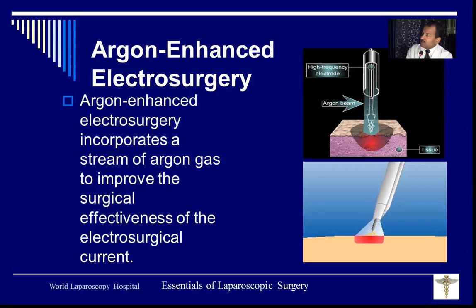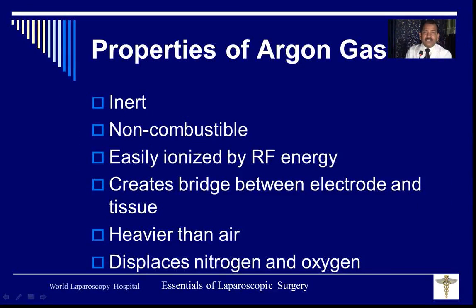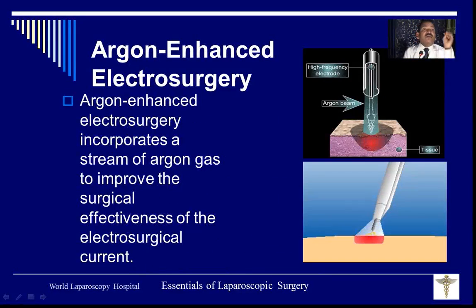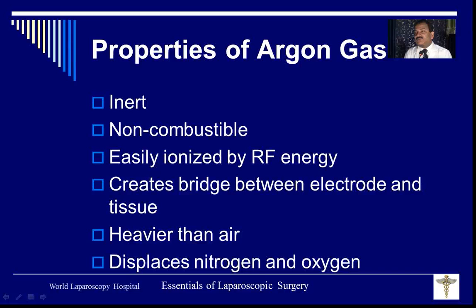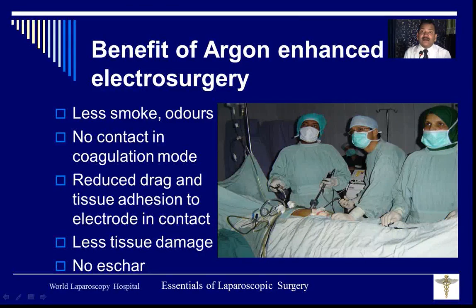In the argon beamer there is a tube outside which will blow the argon gas. Argon gas has a property that it is an inert gas. It is a non-combustible gas. This gas is easily ionized by radio frequency energy. It creates a bridge between electrode and tissue. Means, if you are using the argon beamer, it will take the current from the electrode and pass it to the tissue without touching it. And it is heavier than air, so it displaces nitrogen and oxygen. So what will be the effect? Less smoke, no odor, no contact is required. You can do coagulation from a distance also and reduce drag because gas cannot drag the tissue, no scar formation and less tissue damage.